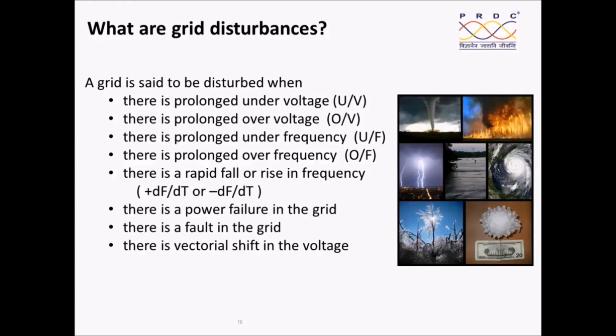What it means is, for transient voltage variations, I should not get islanded. This is very important for us to understand. Whenever there is a transient voltage variation, we should never get islanded. And there is prolonged under voltage. Prolonged under frequency, prolonged over frequency. Today, if you see our grid frequency, we are almost operating from 49.9 Hertz or 49.7 Hertz to 50.05. Very narrow bandwidth we are operating.